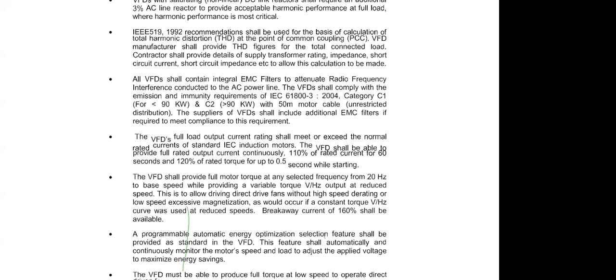So for this total harmonic distortion, the IEEE 519 recommendations say that you have to provide filters to reduce the harmonics. Why have I brought this into today's discussion? Because unknowingly we don't ask our VFD manufacturer how much distortion the VFD they are offering us is creating in the system. Now, you may ask, how does it matter? Of course, it matters, because when you are working with an impurity in the system, you do not know what role it will play in your other equipment.